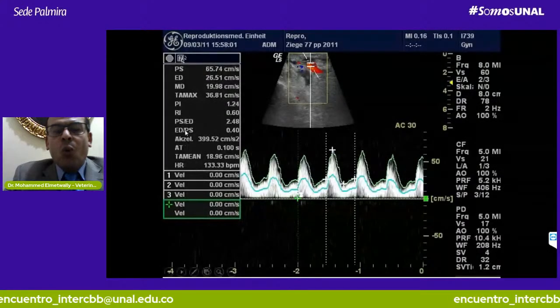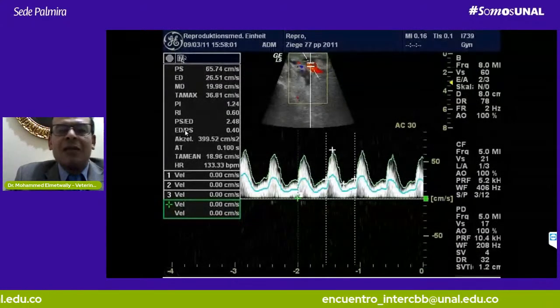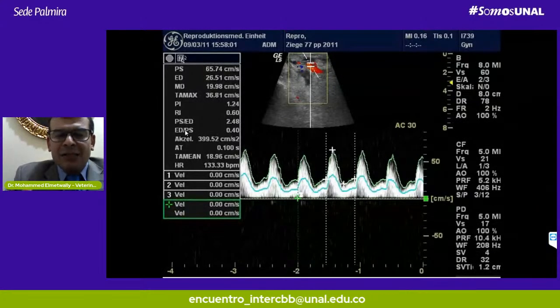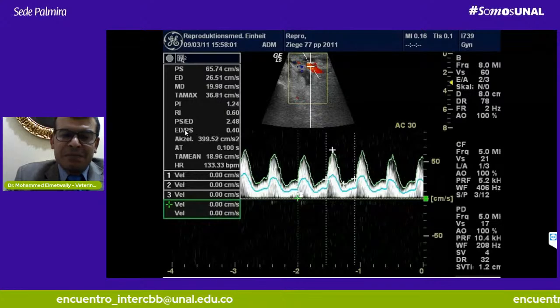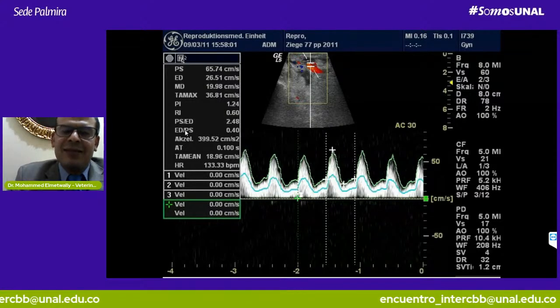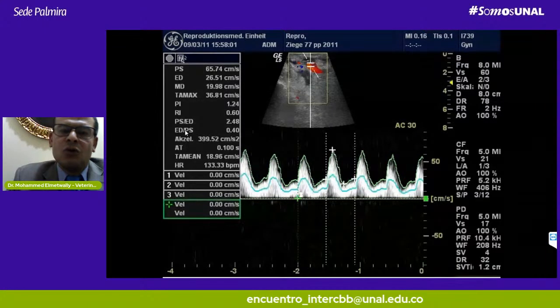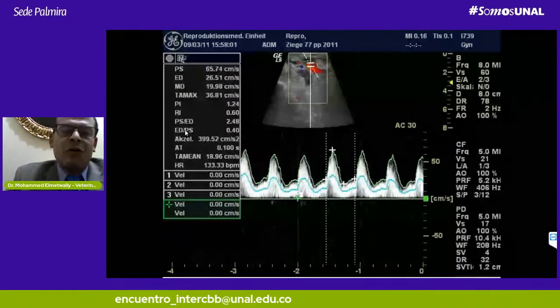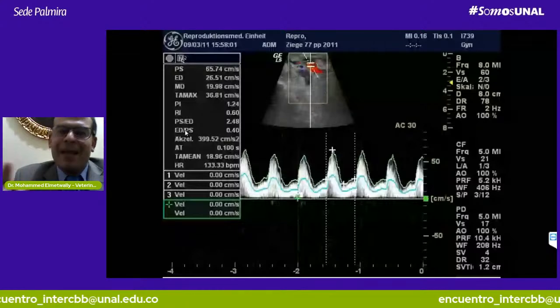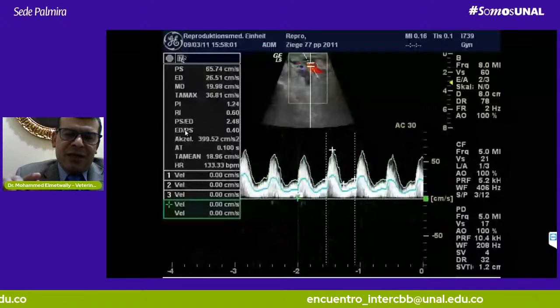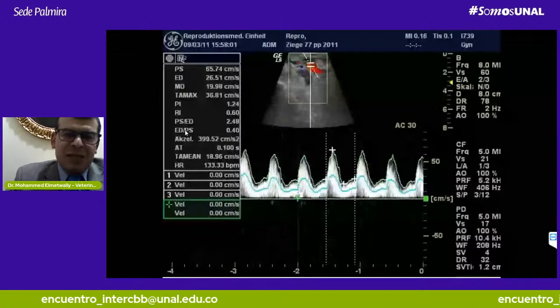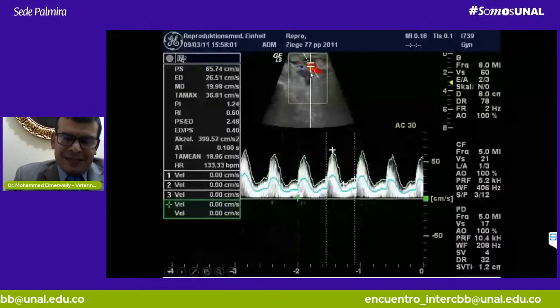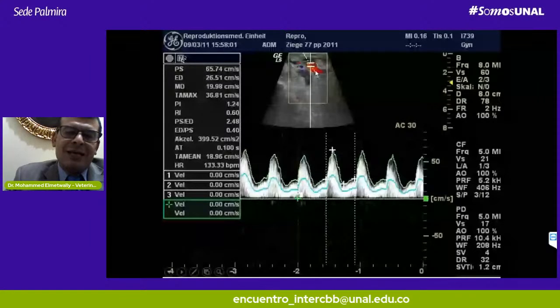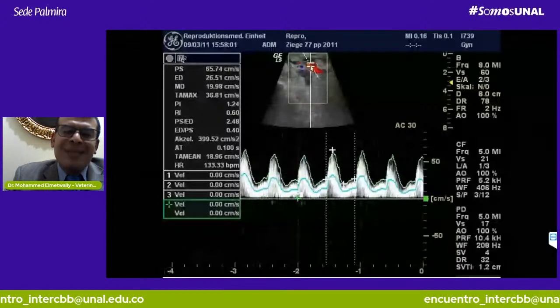Why in this panel we didn't find the blood flow volume? I cannot have the blood flow volume except when I adjust the insonation angle or Doppler angle and the diameter of blood vessels. And this is usually adjusted manually. The adjustment of the insonation angle, as you see in this image, and the diameter of the blood vessels is usually manually adjusted. What does it mean?